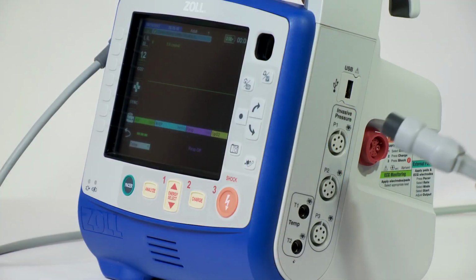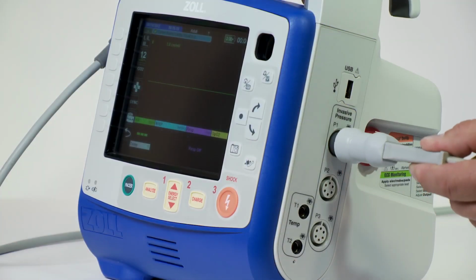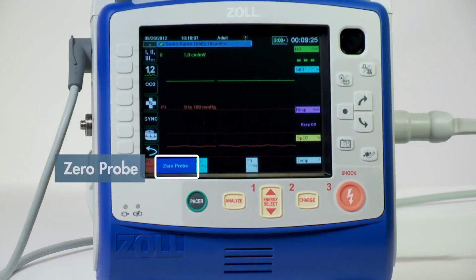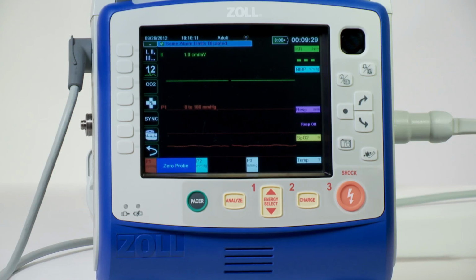If the transducer is a disposable unit with a separate cable, connect the transducer to the transducer cable. Plug the transducer cable into one of the 3 6-pin invasive blood pressure cable connectors on the side of the device. When you plug the transducer cable into the unit, the message Zero Probe appears in the numeric display window for that IBP channel. To ensure that the device measures pressures accurately, you must zero the transducer before each use.